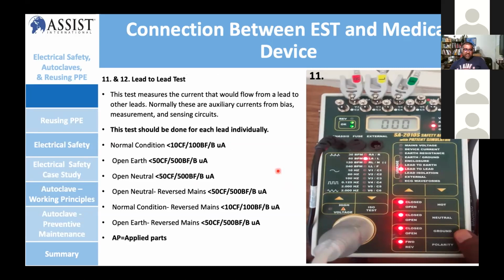So lead to lead. This is another test where you're measuring between the leads. You're comparing lead 1 to lead 2, lead 1 to lead 3. You're comparing each lead, whether there's a leakage between the leads. So this is another method that you need to do individually. But you have to connect all and you're measuring individually, the lead to lead test. You're sensing the current between the leads and checking any current differential and any auxiliary effect on the current bias. So this is the range.